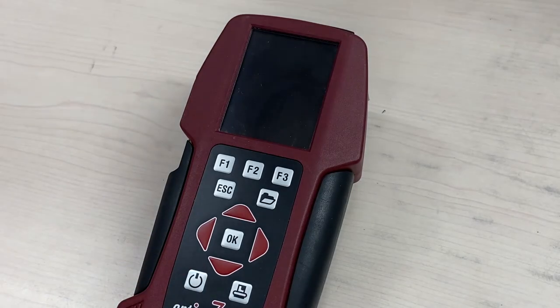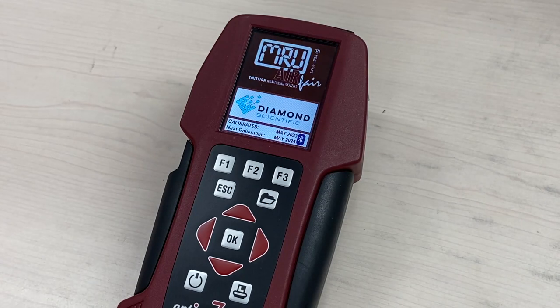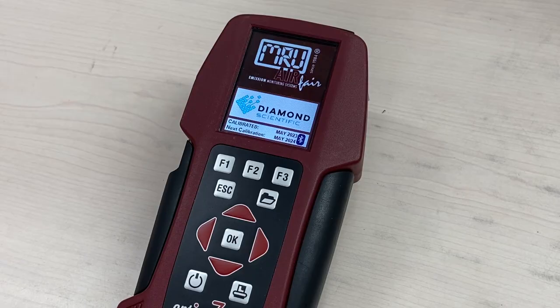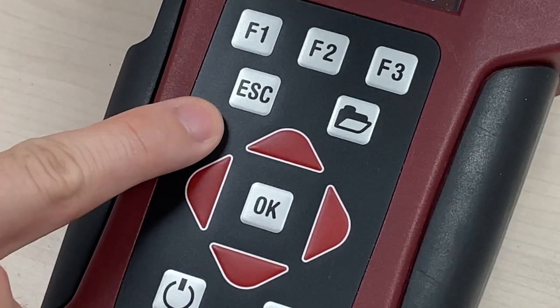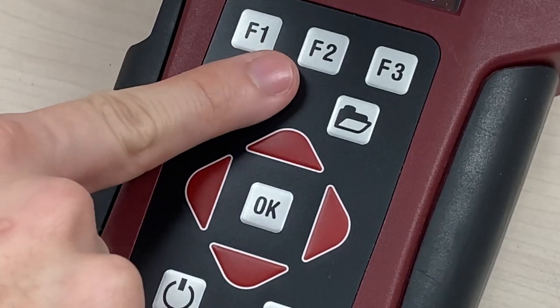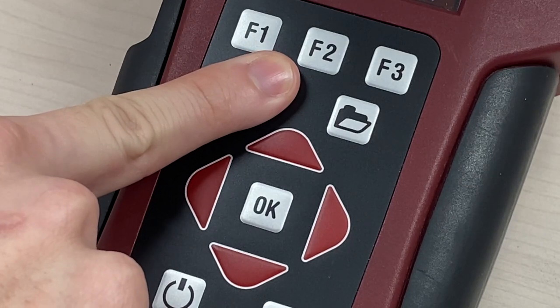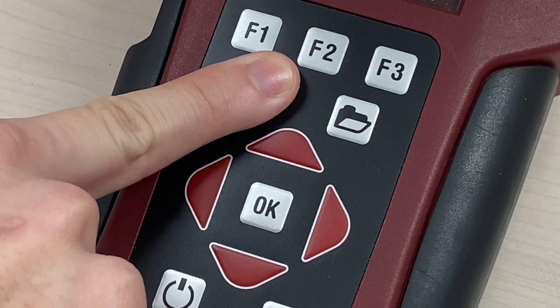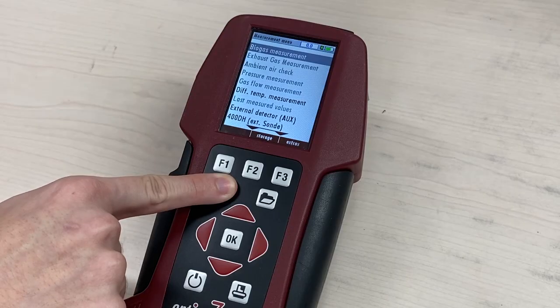Power up your unit. You can allow the instrument to automatically zero. To skip the zeroing, press the ESC key for about 8 seconds, or until the instrument beeps, notifying you that the pump has stopped.